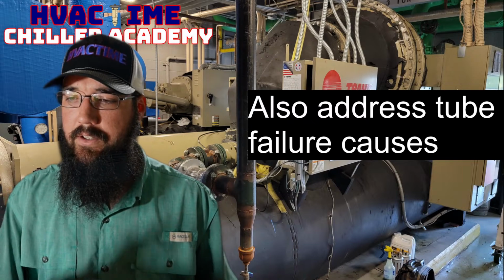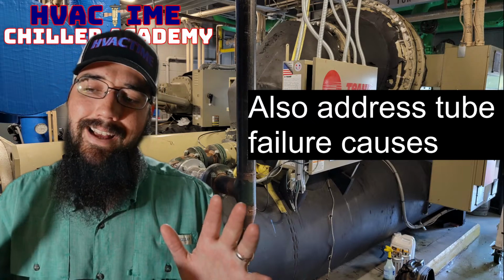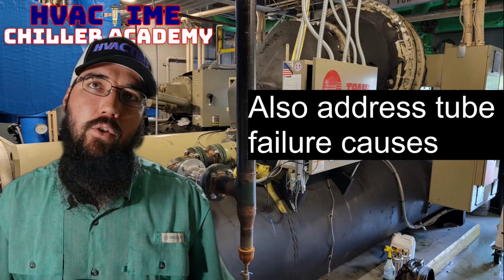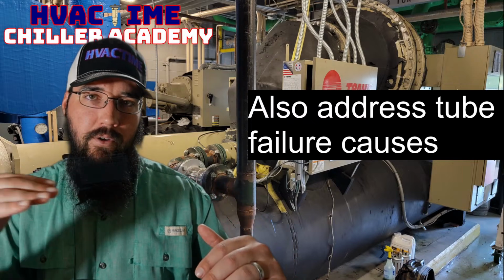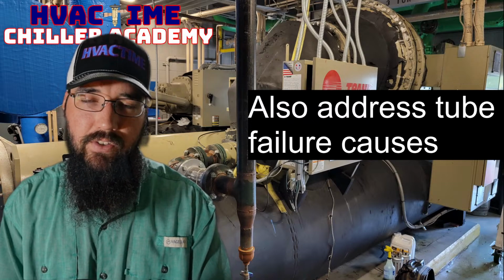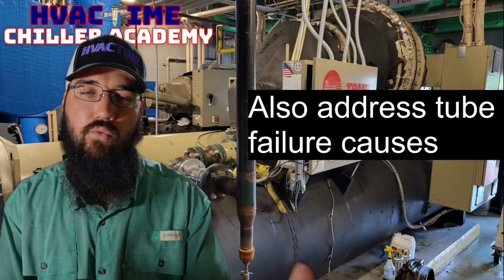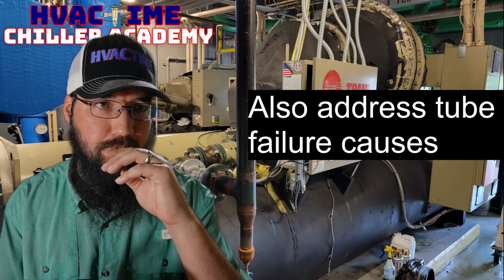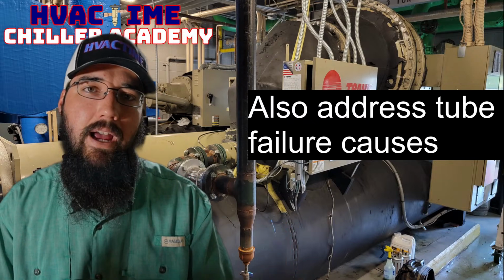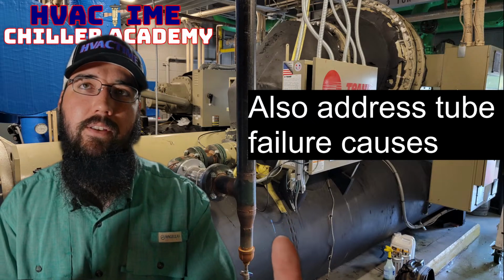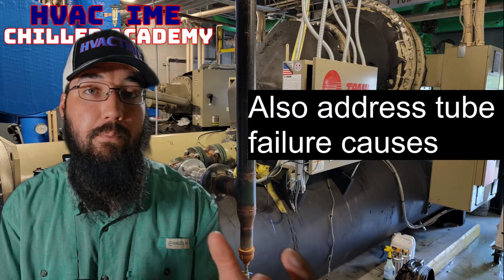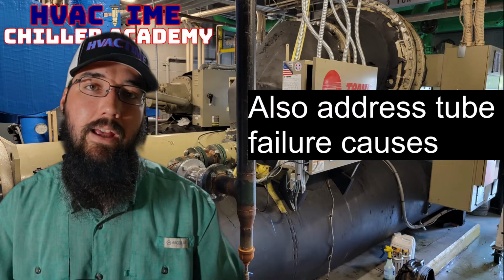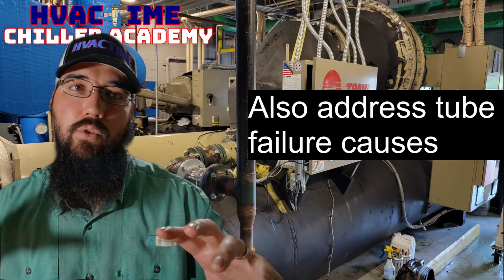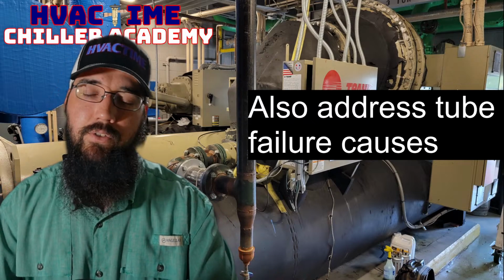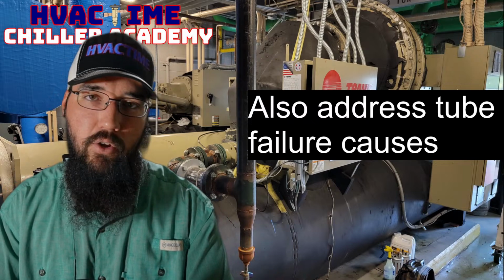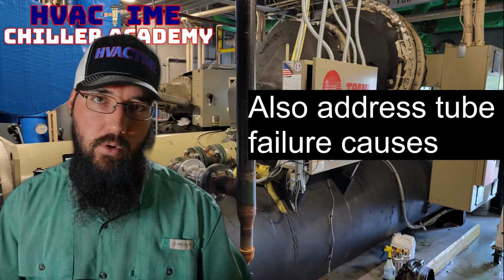Another one would be, and I see Henry mentioned it there, saddle wear. These tubes that are going through the heat exchangers, they're sitting in a set of racks, if you will. Let's call it that. And these racks can end up becoming a rubbing point, depending on refrigerant conditions, depending on flow conditions, water flow.